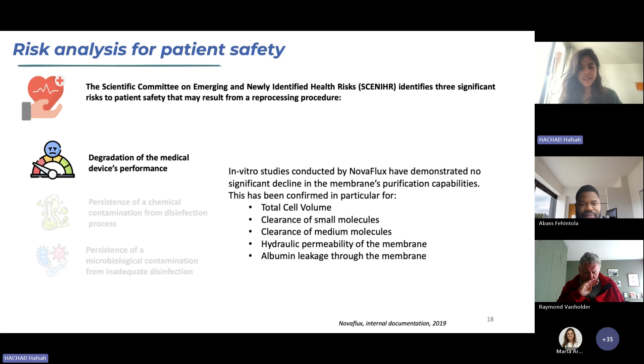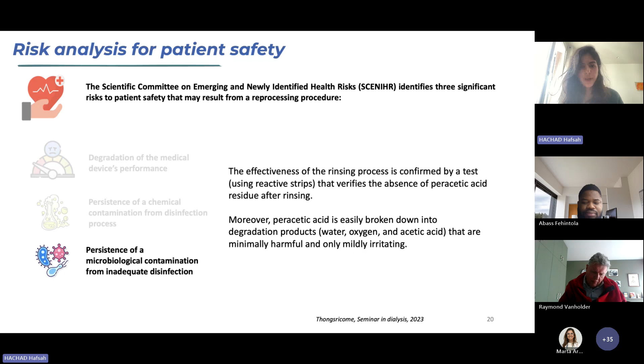And the system has been used for 3 years in daily dialysis facilities, and no problems with the safety of patients have been reported. Regarding the persistence of a chemical contamination, the effectiveness of the rinsing process has to be confirmed by a test using reactive strips that verifies the absence of peracetic acid residues after each rinsing. And moreover, peracetic acid is easily broken down into degradation products like water and acetic acid, which is kind of the vinegar, and that are really minimally harmful and mildly irritating. Regarding the persistence of the microbiological contamination, as I was saying, no problem has been reported from the use of NovaFlux in the US.